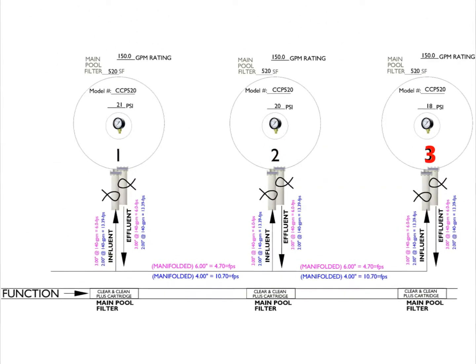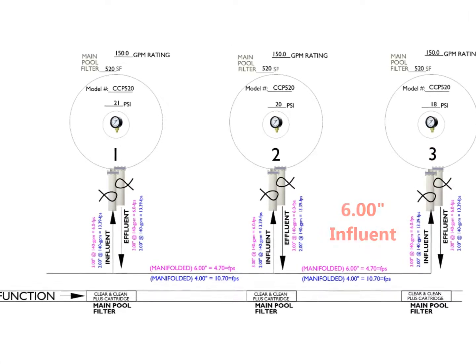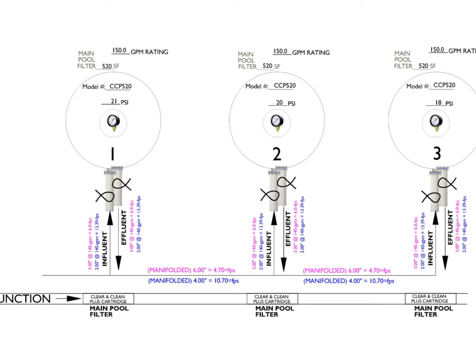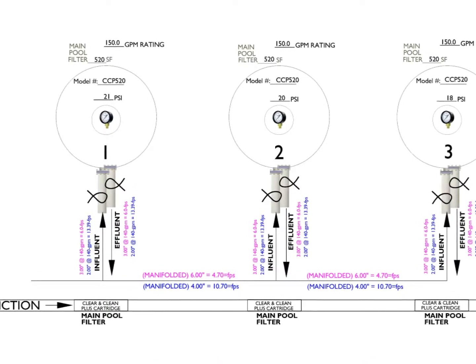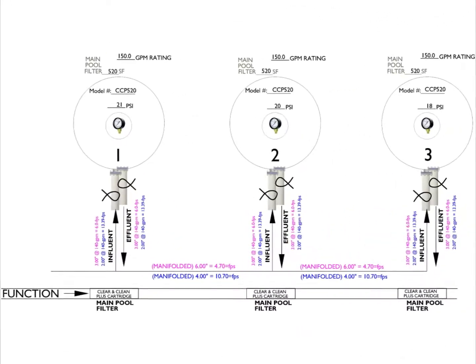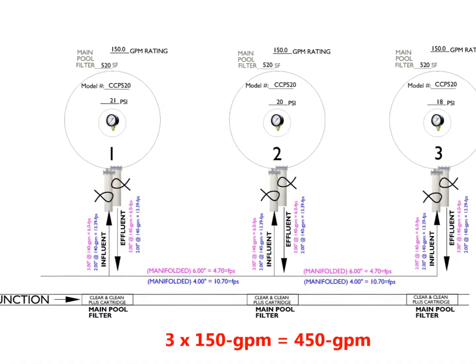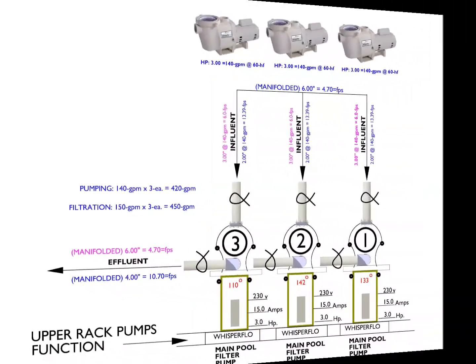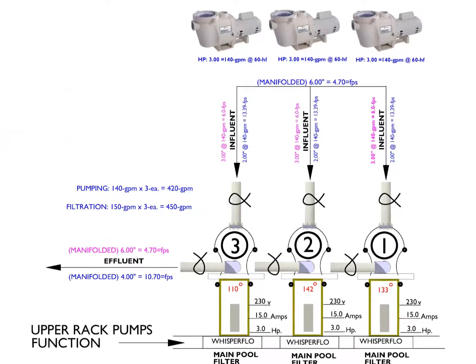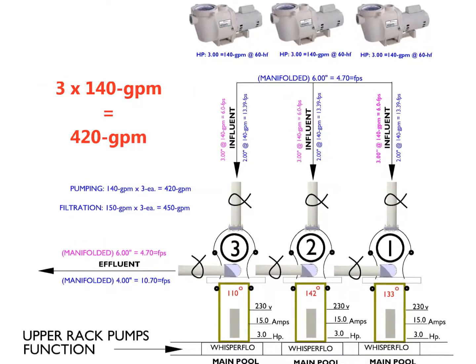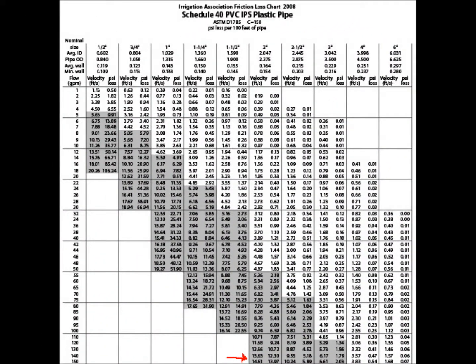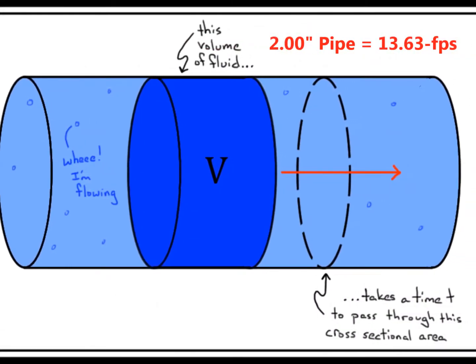There are three Clear and Clean Plus 520 square foot cartridge filters plumbed into one common 6-inch influent and 4-inch effluent manifold. These manifolds connect to the filters with 2-inch piping that causes considerable restriction at the combined pumping flow rate. The combined maximum flow rate for all three filters is 450 gallons per minute — 3 times 150 gallons per minute each — which is in balance, but the friction loss characteristics for the 2-inch pipe size are excessive due to hydraulic head losses at the flow rate velocity.